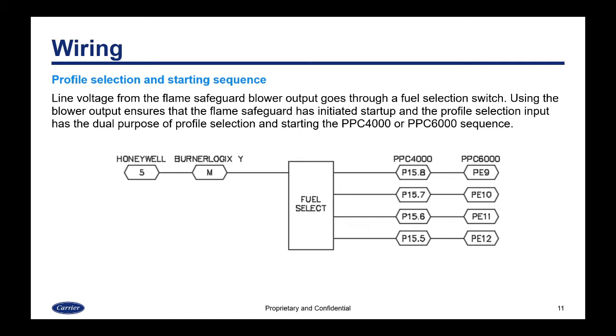In wiring, this is how we start: profile selection and starting sequence. Line voltage from the flame safeguard blower output goes through a fuel selection switch. Using the blower output ensures that the flame safeguard has initiated startup, and the profile selection input has the dual purpose of profile selection and starting the PPC4000 or PPC6000 sequence. You can see in this portion of the wiring that the voltage comes out from the blower output and goes through the fuel select switch to one of the fuel selection options.